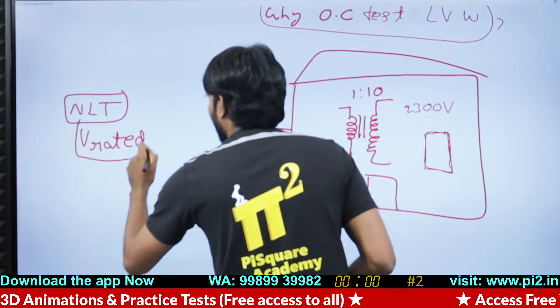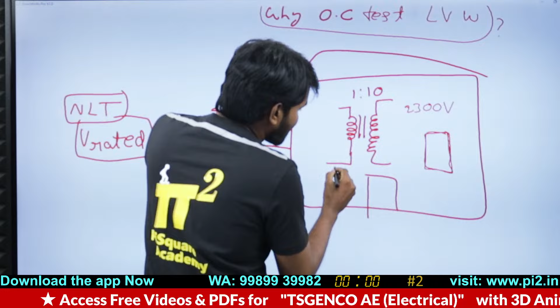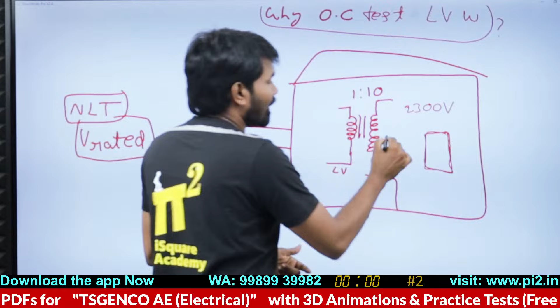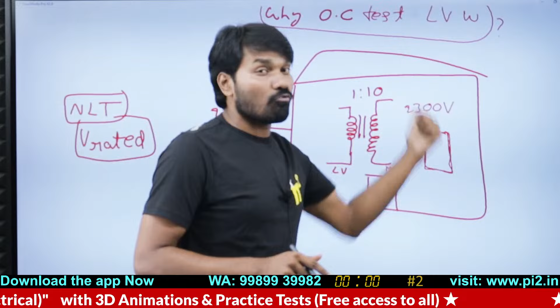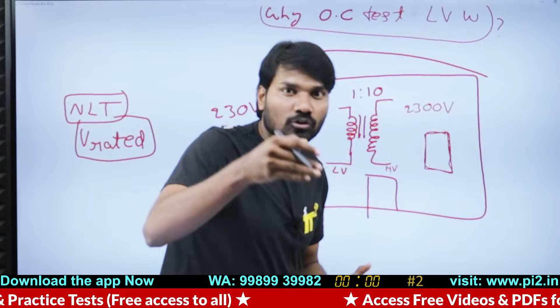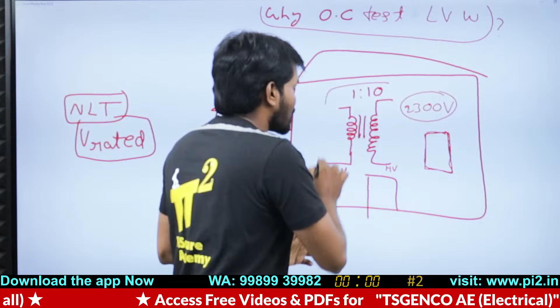I want to test this transformer. In order to test it at the low voltage side, I will have to give 230 volts. If I have to test the same transformer at the high voltage side, I need 2300 volts. But my laboratory does not have 2300 volts - that is why I purchased this transformer box in the first place. Now to test this box, it requires 2300 volts - where do I have it? To test it, I'll have to buy another transformer. That's the most stupid thing. So why conduct the test at the HV side?